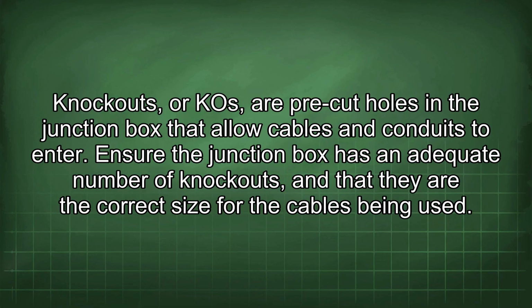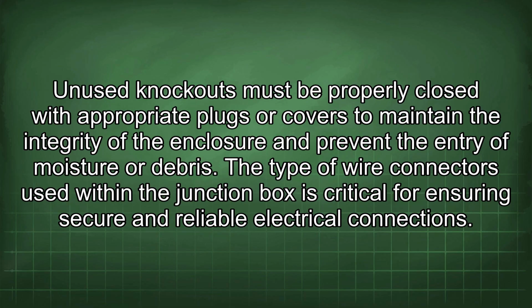Knockouts, or KOs, are pre-cut holes in the junction box that allow cables and conduits to enter. Ensure the junction box has an adequate number of knockouts and that they are the correct size for the cables being used. Unused knockouts must be properly closed with appropriate plugs or covers to maintain the integrity of the enclosure and prevent the entry of moisture or debris.